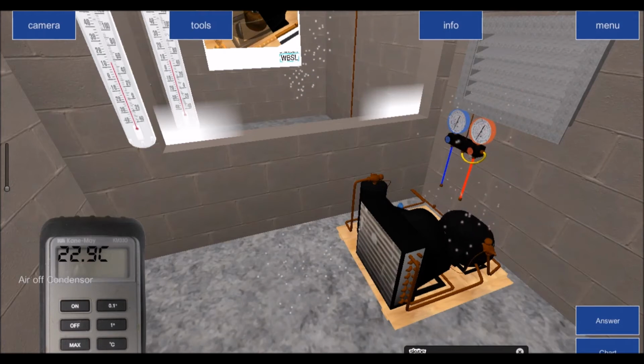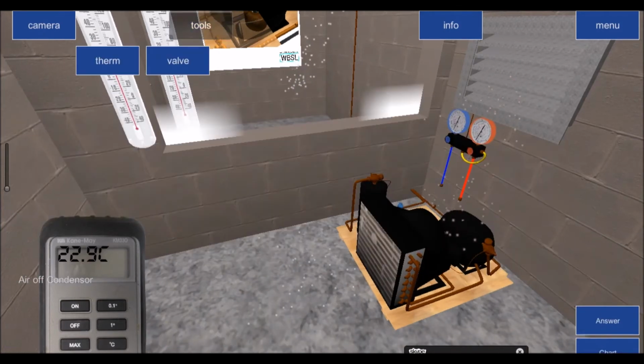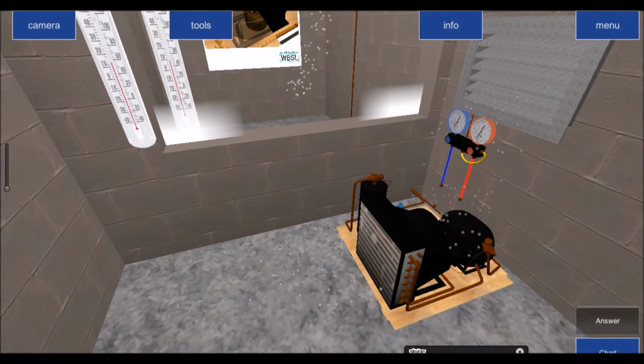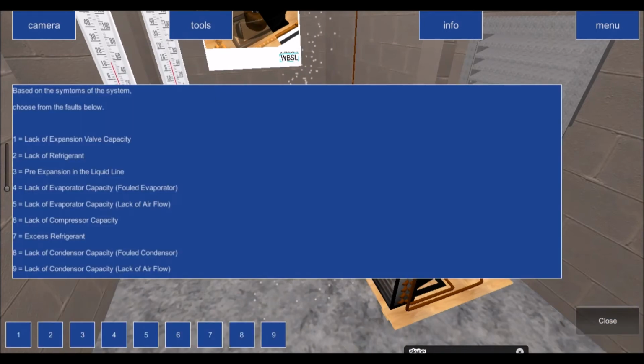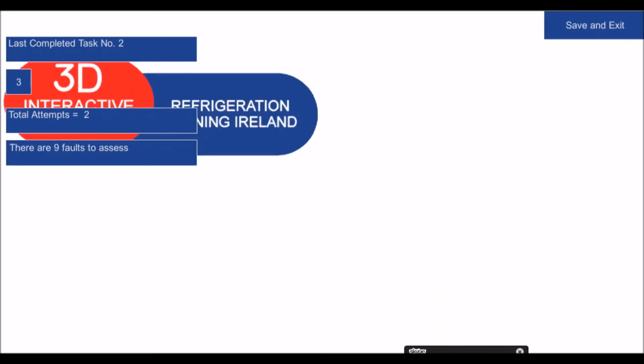Anyway, getting back. So then we go and we do our answer, and we say that it's lack of condenser capacity, and we say that it's a heat exchanger fouled, and we discovered that based on the delta T being quite small across it. So we go down through our list here: lack of expansion valve capacity, lack of refrigerant, lack of expansion valve, lack of evaporator, lack of compressor, lack of condenser capacity, fouled condenser, lack of condenser capacity, lack of airflow. So we're going to go with number 8. See if we're right. Went to number 8.